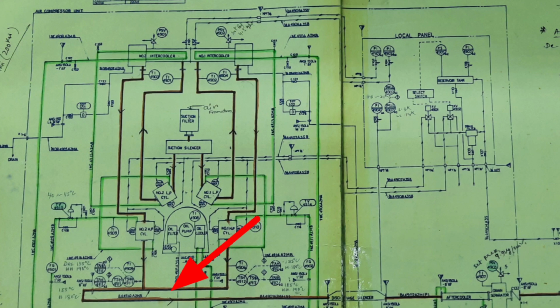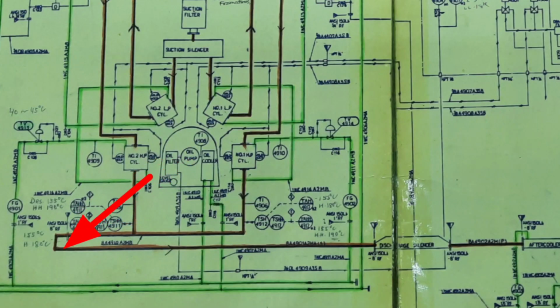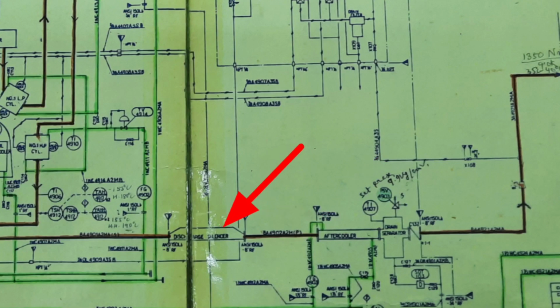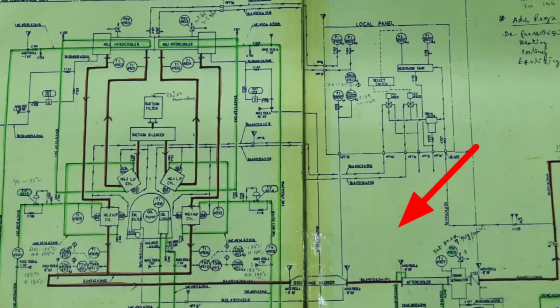By this way it will discharge, and slowly this air will go to the discharge silencer. So the first one is the suction silencer, and this is the discharge silencer. After the discharge silencer it will go to the after cooler. After that it will go to the drain separator, and finally by this check valve it will go to the air receiver.